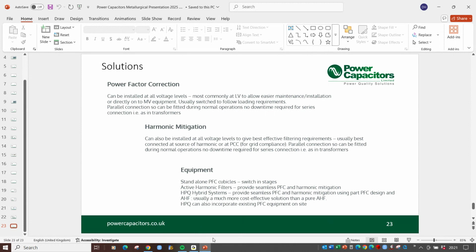Does the addition of more than one transformer in a circuit have a cumulative effect on the impact of the harmonic? Not really, because the transformers are basically a source of current for your system. Because they're joined for voltage, the voltage will stay the same across those two transformers. And that's why the network operators are so worried about the harmonics, because it's the voltage that changes. So the voltage will go onto their grid through both of those transformers. It's a really good question, because most of the time with components, you split the current or you split the voltage. Whereas in this instance, it doesn't.